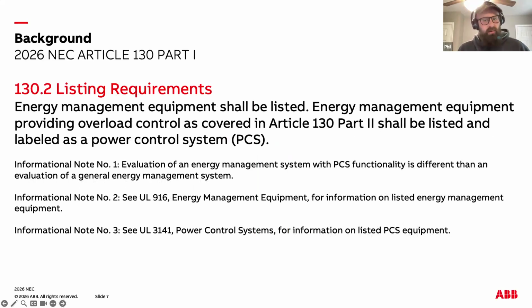Just to touch on some of the important codes in the new Article 130. Article 130.1, which is not pictured, is about scope. It basically just says that the article applies to the installation of energy management systems. So I'm going to skip over that one. But 130.2 is where it gets kind of interesting. It's about listing requirements. Specifically, it says energy management equipment shall be listed to UL 916, and power control systems, which are defined in Part 2 of Article 130, must be listed to UL 3141.